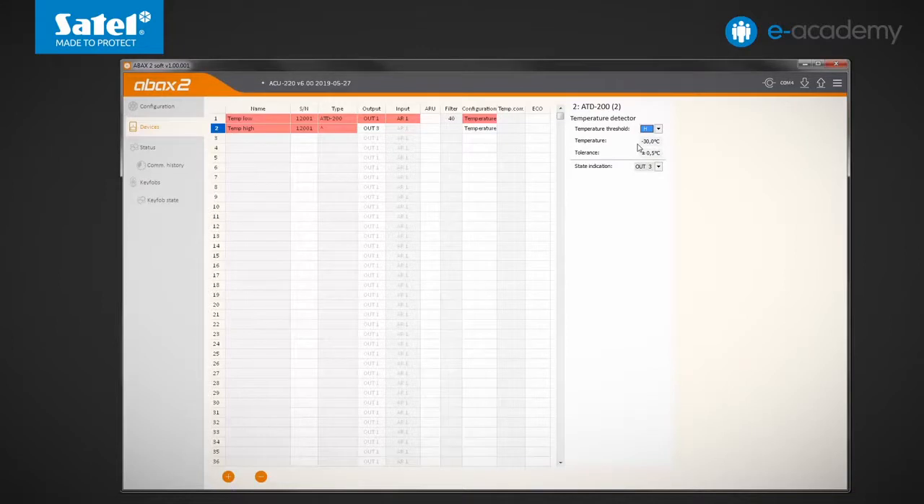You can enter a number from the range of minus 30 to plus 70 as the temperature value. You can also specify the tolerance by entering a number from 0.5 to 10. Unlike the other operating modes available in the ATD-200, in the case of the temperature detector there is no need to switch between passive and active states.